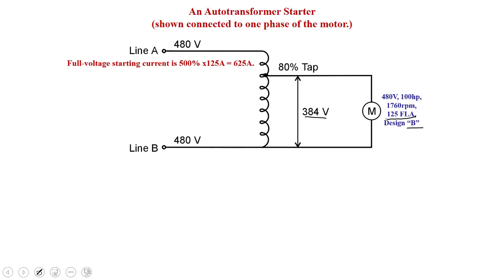625 amps for most electrical services is definitely going to dim the lights and wreak havoc on trying to start it up. It may cause other machines within that building to drop out because the voltage will be so reduced. There's a huge volt drop on your transformers and all your lines. So full voltage starting VA is going to be 480 volts times my 625 amp inrush, so as much as 300 kVA to get this thing going. That's quite a bit.